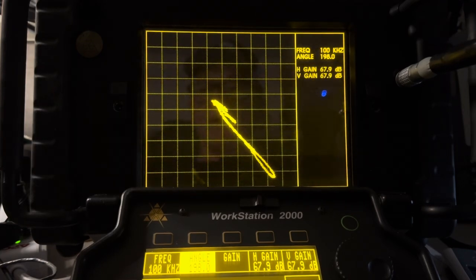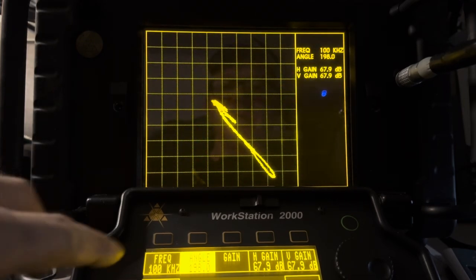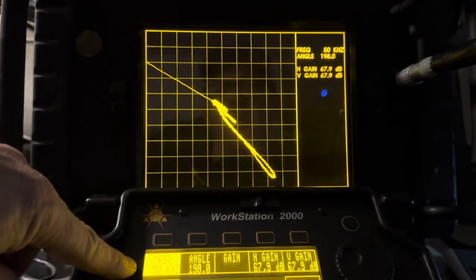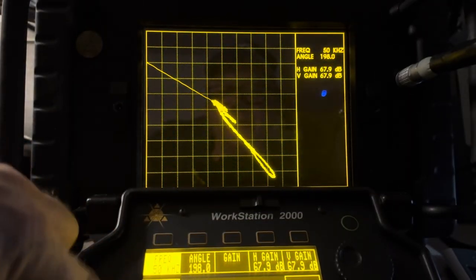Well, it's not cooperating. So the coil parameters are a bit different on this encircling coil, so I think I have to drop my test frequency. Wide coils just don't operate that well at higher frequencies.